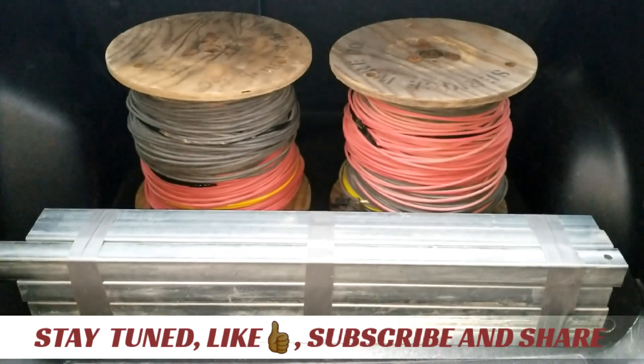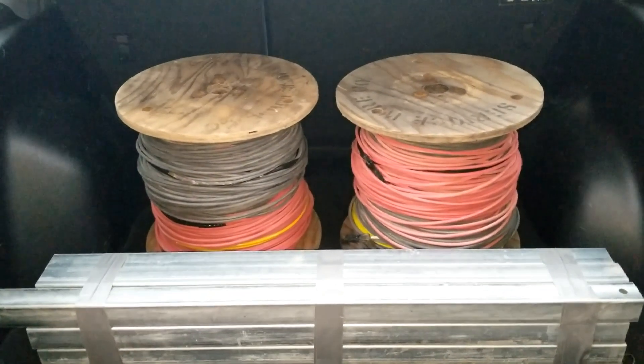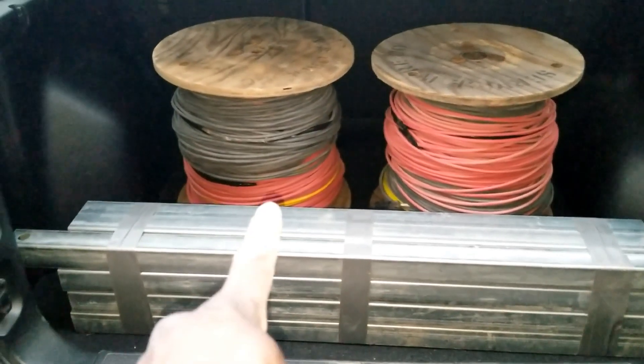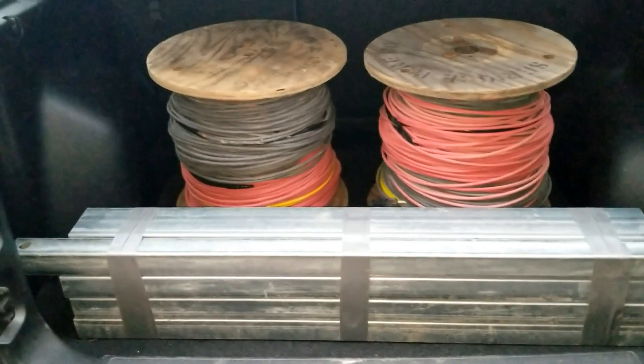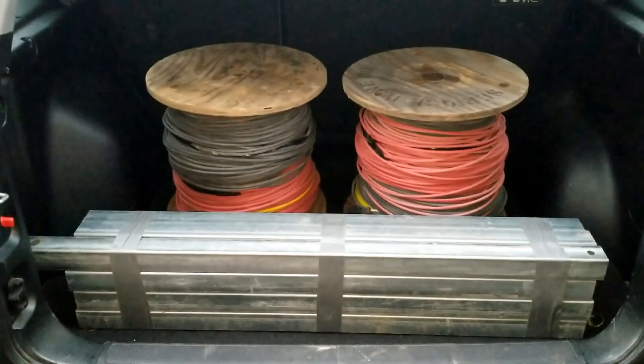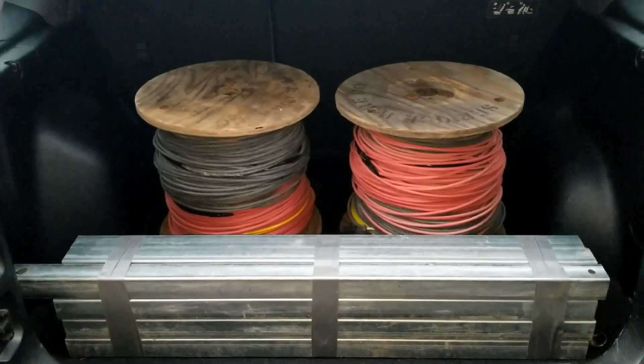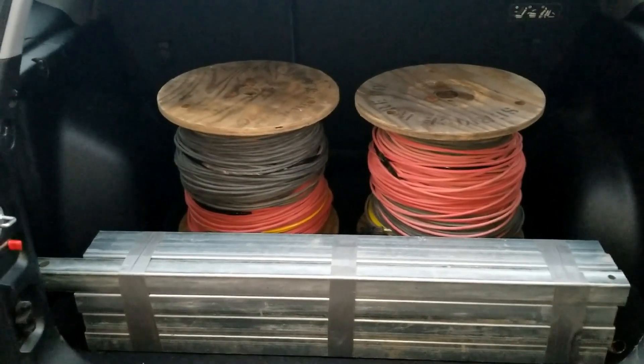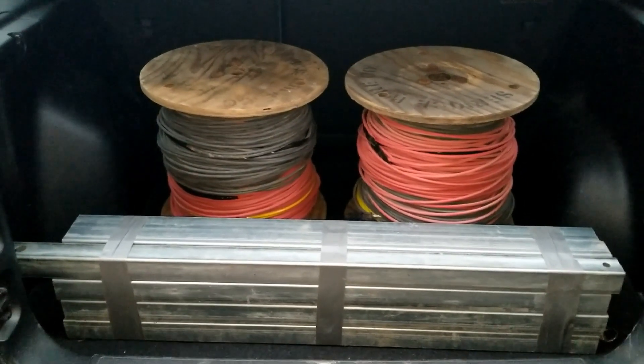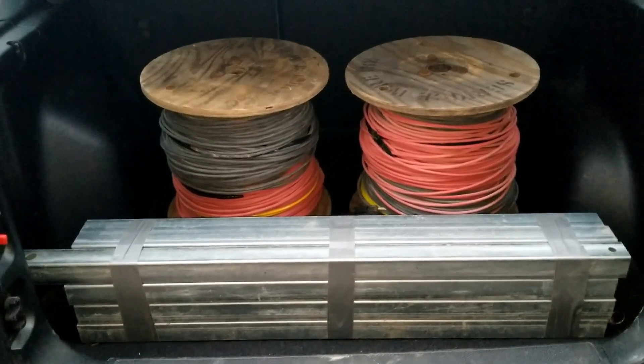What you're seeing right now is what I just picked up — two spools of cable. These wires are already wound in pairs; you see the black and the red. I'm having 12 strings, 12 strings of 215 feet of cable. Each string is 215 feet long. So where I'm going to set the array, that's the distance — 215 feet long for each string.